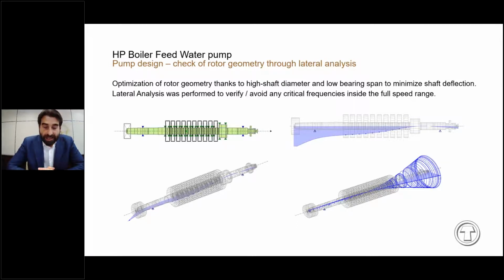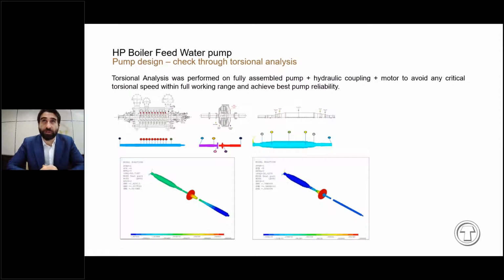And the lateral analysis has been made in order to check and avoid any critical frequencies inside the full speed range, which in this case is quite wide. For the same reason, we have also made the torsional analysis, which has been performed not only on the pump shaft but also on the whole train. So it is composed of the rotor of the pump, the rotor of the hydraulic coupling, and the rotor of the electric motor connected together with the flexible couplings. The aim of this analysis is to avoid any dangerous torsional resonances.